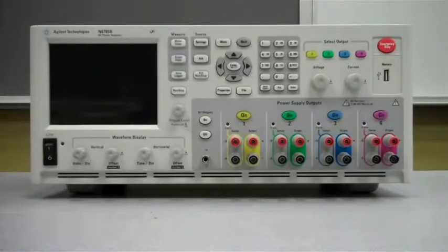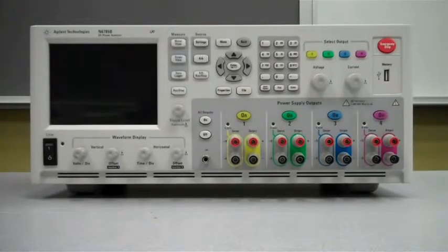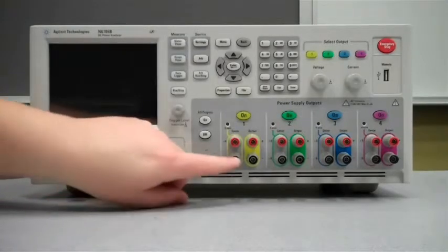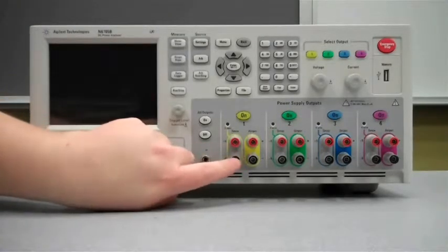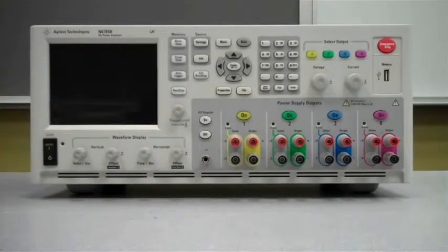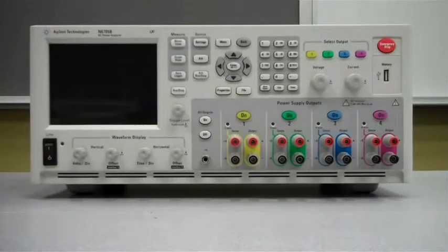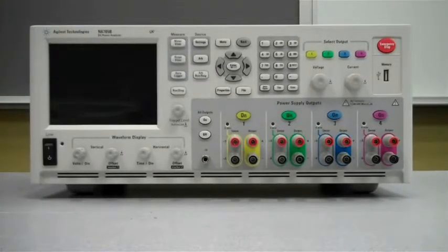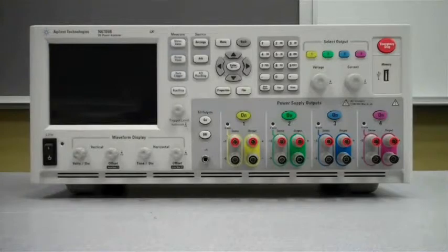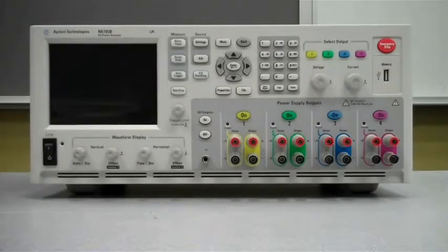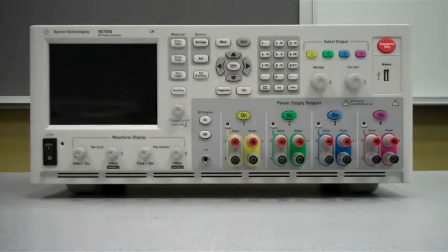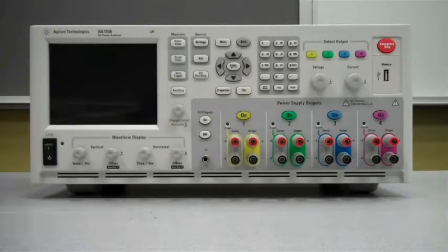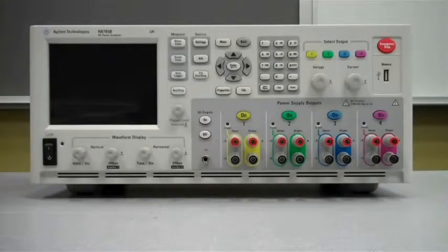Here's a closer look at the front panel of the B mainframe. The first thing on the front panel we want to talk about is the assembly behind the binding post here. We lowered the capacitance in order to handle the faster transient and higher programming measurement accuracy for the new N6780 SMU modules. And again, all the specifications for the modules will be in the manuals on the website at agilent.com.